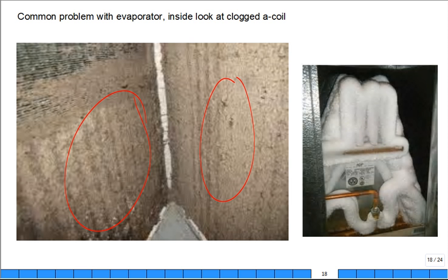Now also when it clogs up, the refrigerant can't cool down. And somebody was telling me, yeah, my A coil freezes up. There's a picture of a frozen up A coil due to lack of airflow across it. Right? It freezes up. Anybody had that experience? No? A couple? Yeah. Then you have to wait for it to defrost.